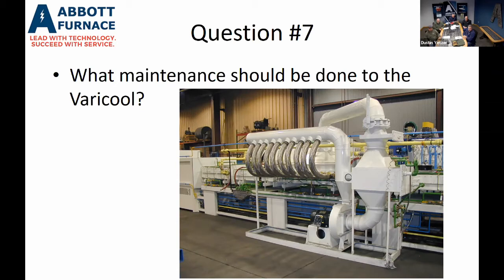Right behind the heat exchanger housing, there's a magnehelic gauge where we measure differential pressure above and below that heat exchanger. As that pressure difference increases, the magnehelic reading increases, and that's also a good factor to tell us it's starting to get plugged, and we better go in and clean that heat exchanger and that filter.